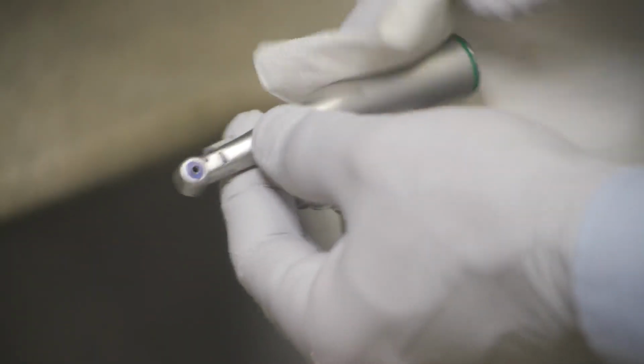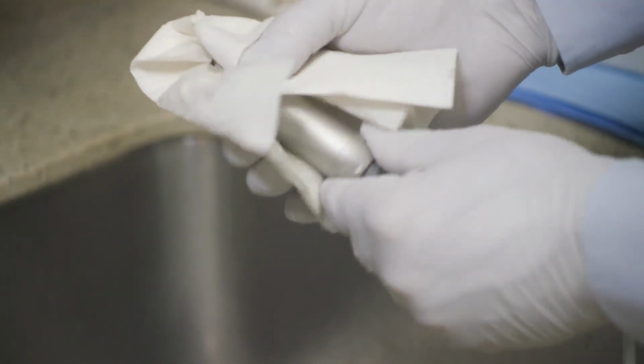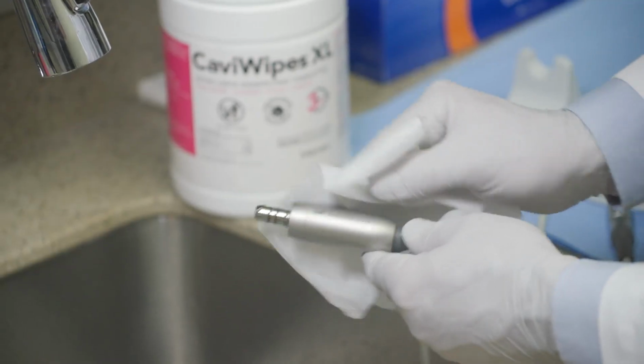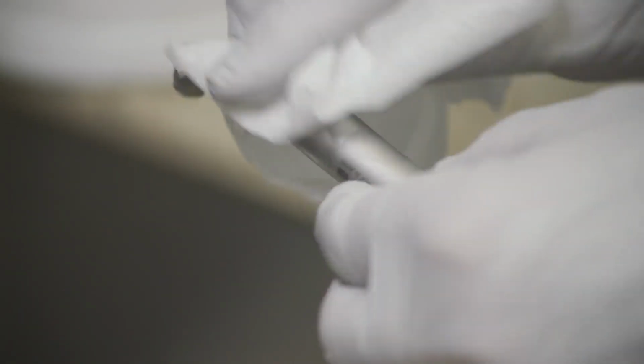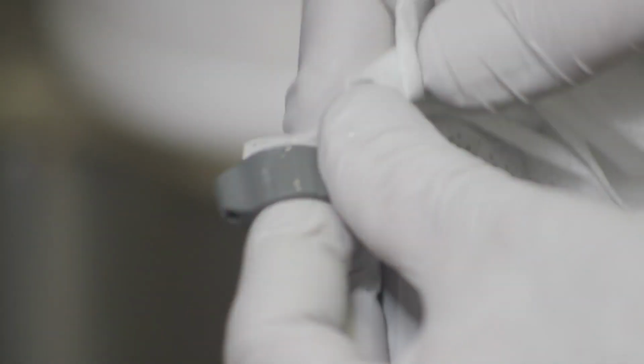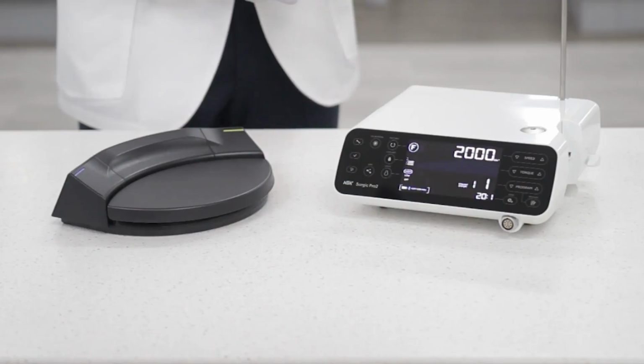Wipe the products dry using a piece of clean cloth or paper towel. Remove the protection plug from the motor and cord. You can disinfect the surface of the products using disinfectant wipes or an ethanol moistened cloth for 2 minutes. To clean and disinfect the control unit and foot control, use an ethanol moistened cloth only.